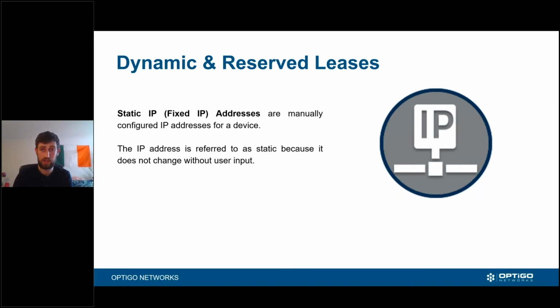So you can go to the next slide there, Ping, unless you have other notes around static IP addresses. In the building automation or smart building operational technology space, we tend to use static IP addresses. Looking at 10 years ago, when we had a few tens, maybe a couple hundred devices, that approach was okay. Now we're looking at every VAV, every lighting controller, every device, and we're talking about thousands and thousands. Our recommendation is to try to use dynamic and reserved IP addresses.